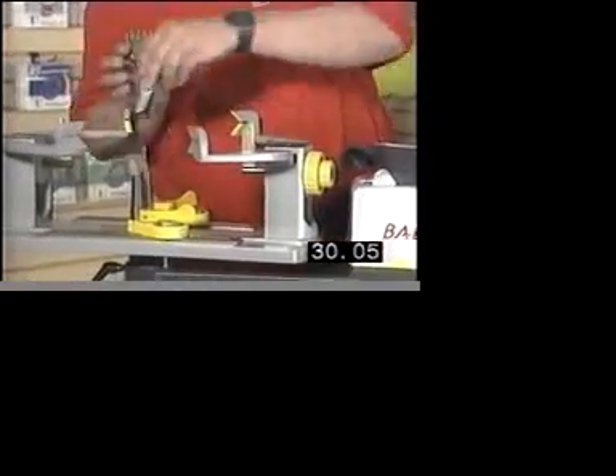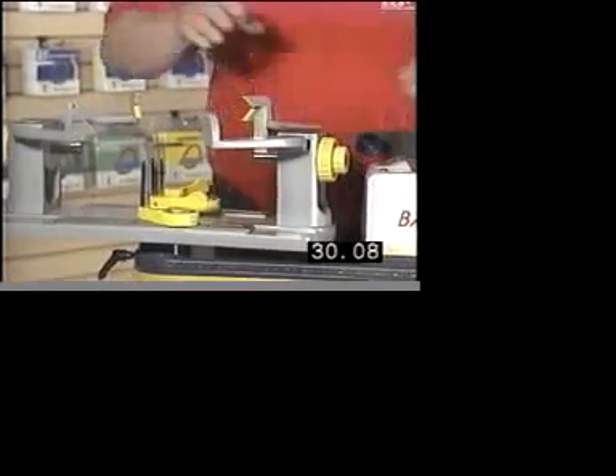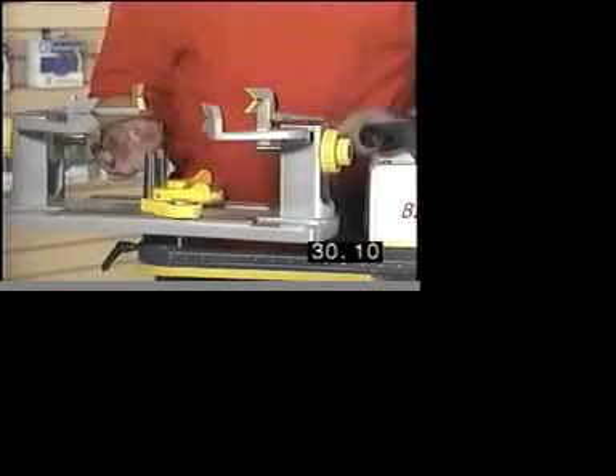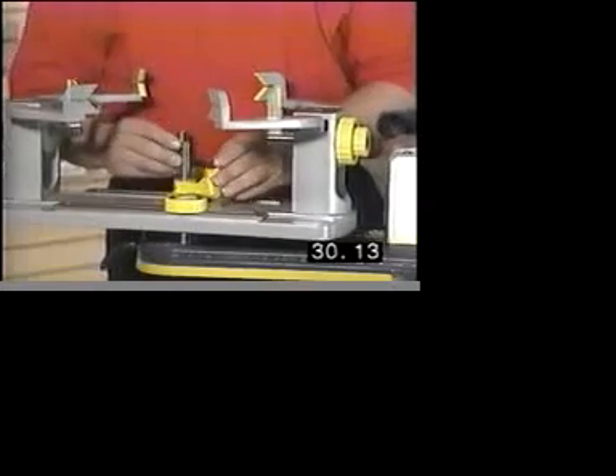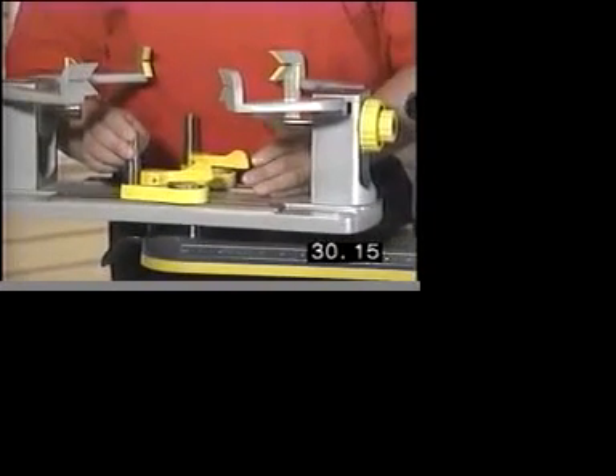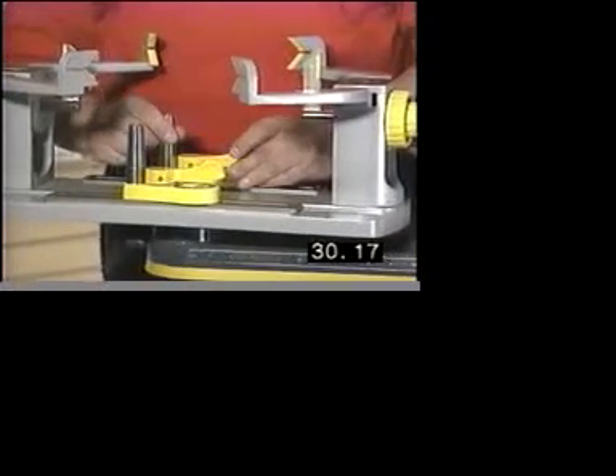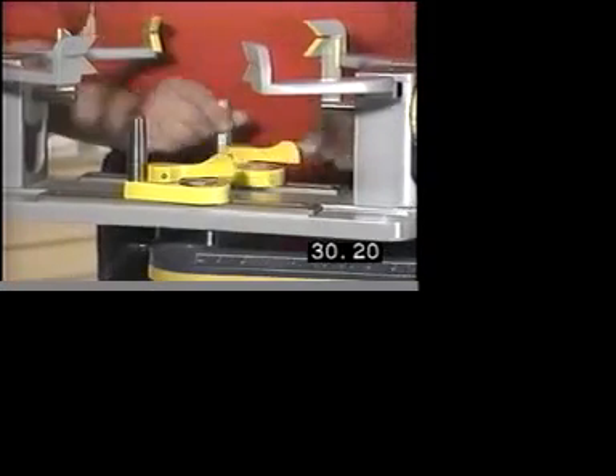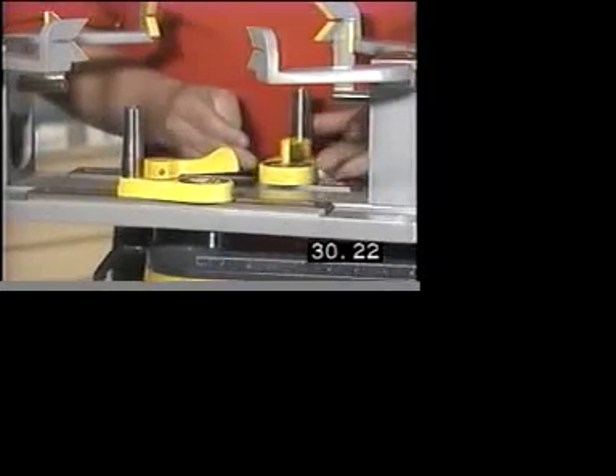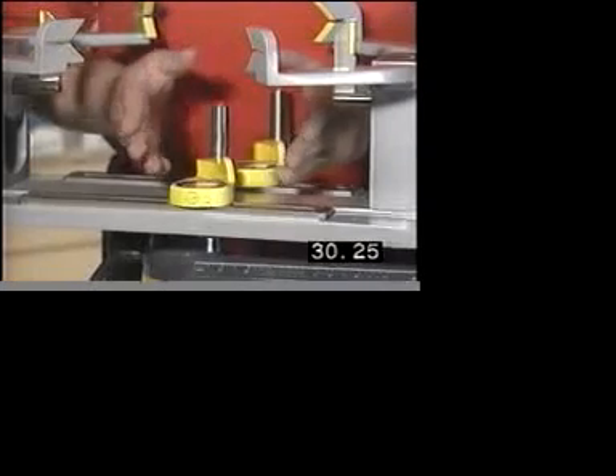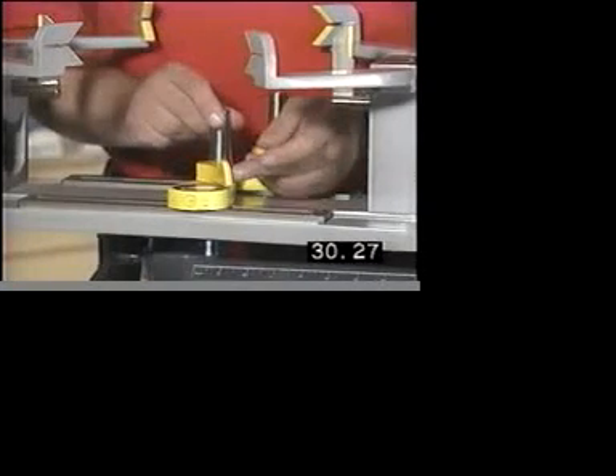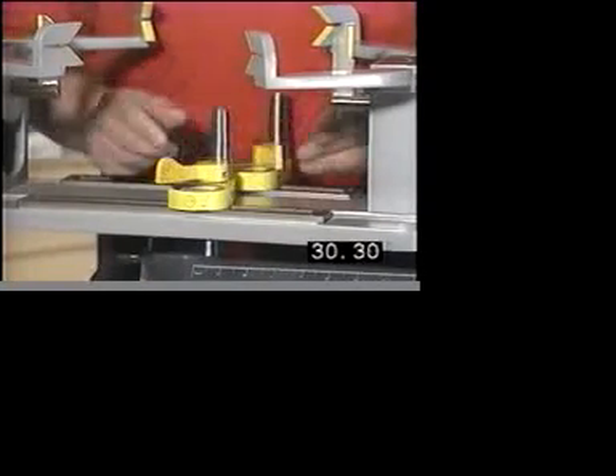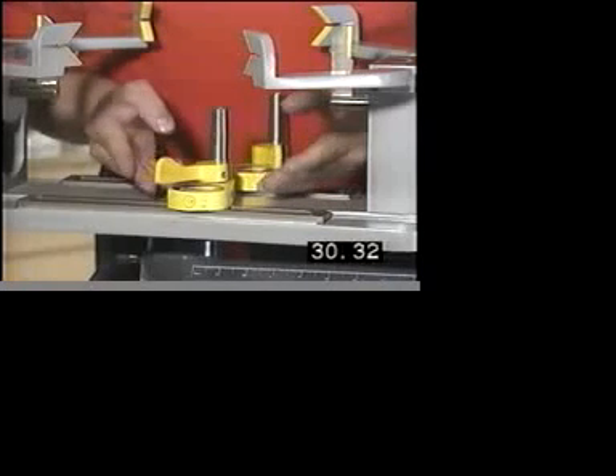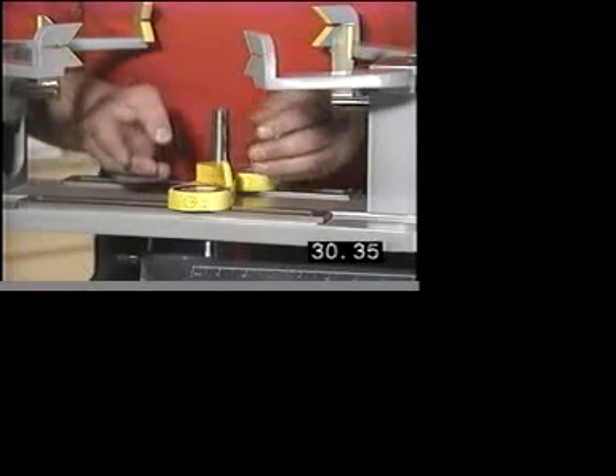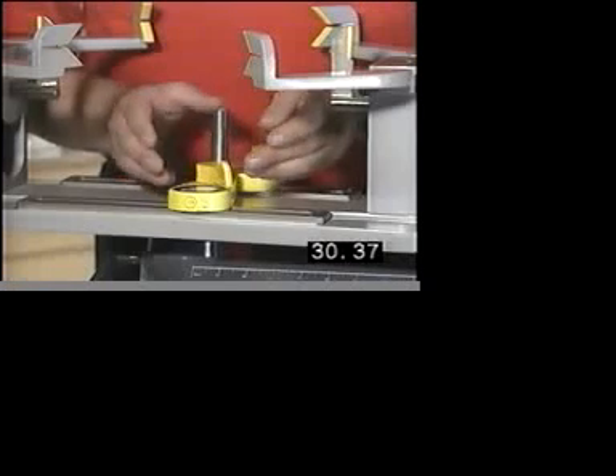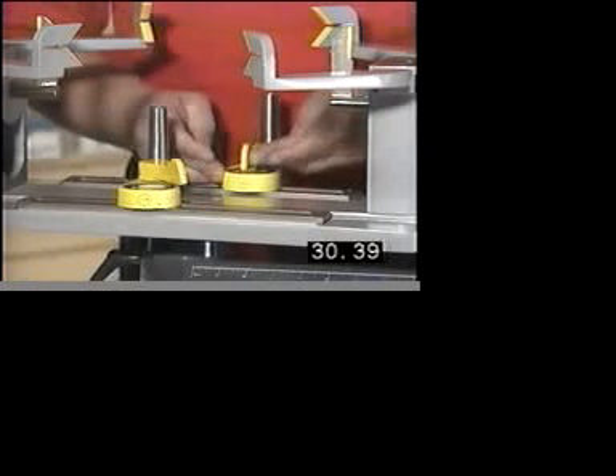First of all, I'm going to get these center clamps out of the way so that we're just looking at the clamp bases. One of the biggest things that can go wrong is over tightening the clamp; eventually it's not going to lock in the center anymore. This one is locking directly in the center. This one I've misadjusted so that you can see what the problem would be. If your clamp is locking farther past center, obviously it's not going to hold as well and it's not going to flip back as easily.